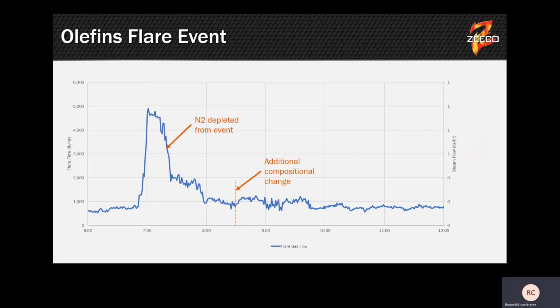And so what we did was, again, we're trying to help operators understand how to monetize these kinds of controls. And this comes from an example this year in an olefins plant here in the USA, where one of these devices was deployed, and we spent some time tuning it. So what we wanted to capture is a small olefins excursion at a facility. It has its baseline flow. It had some kind of upset, not huge, 5,000 pounds an hour. And then that was curtailed within the plant and brought back to baseline.